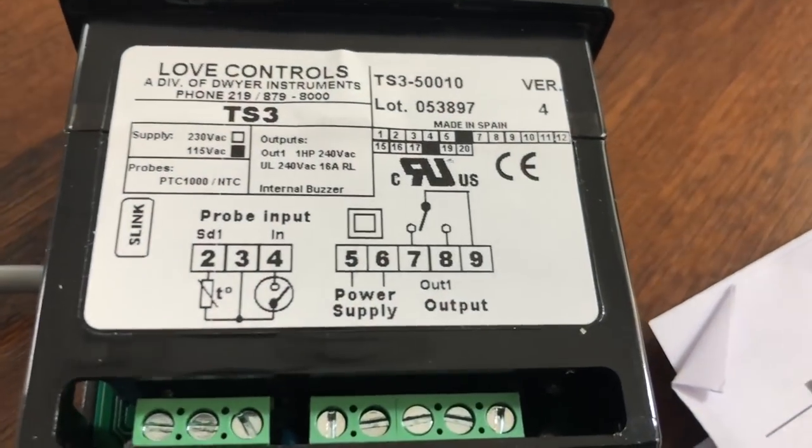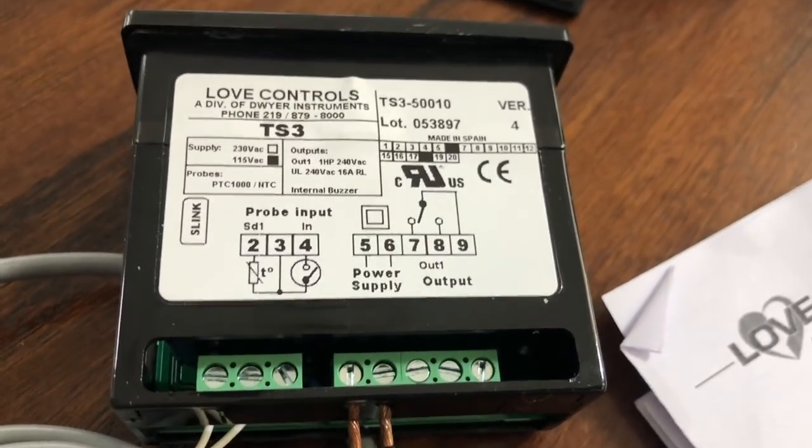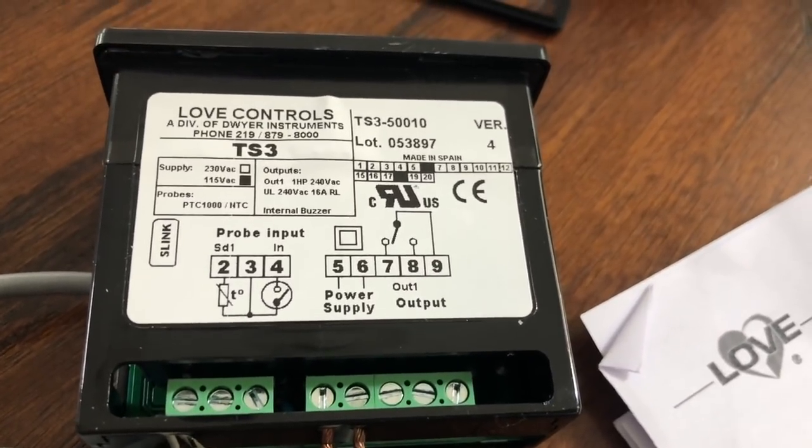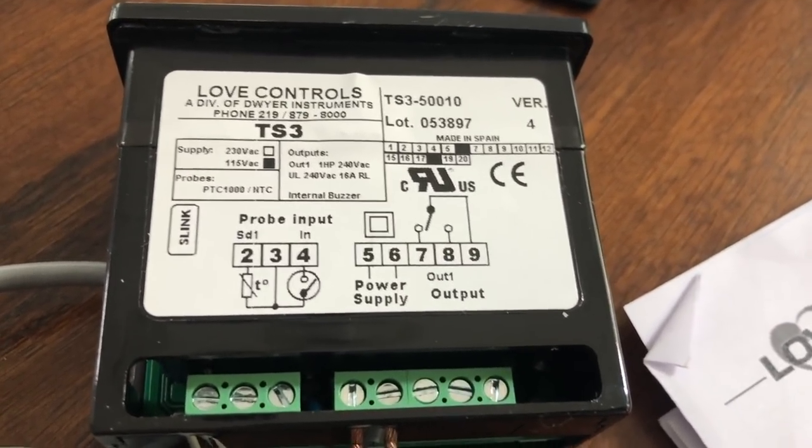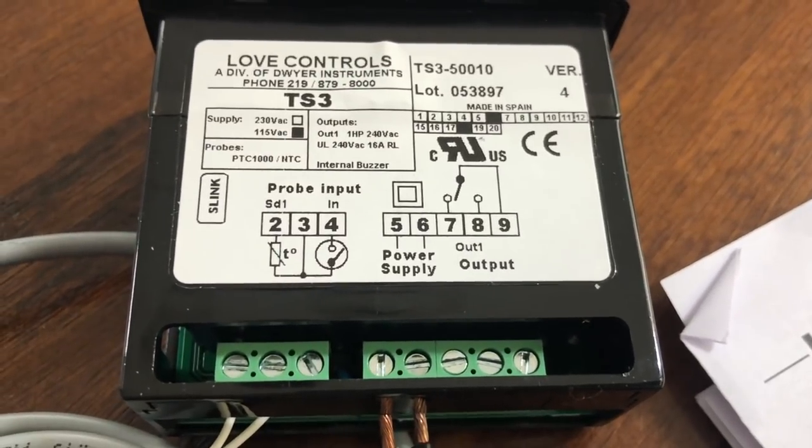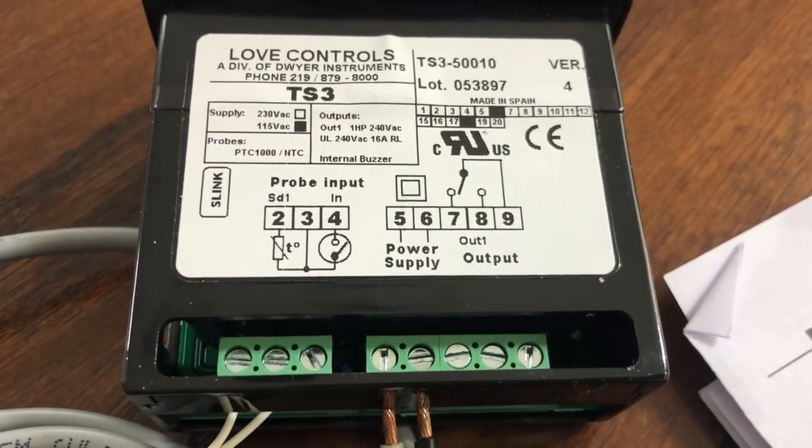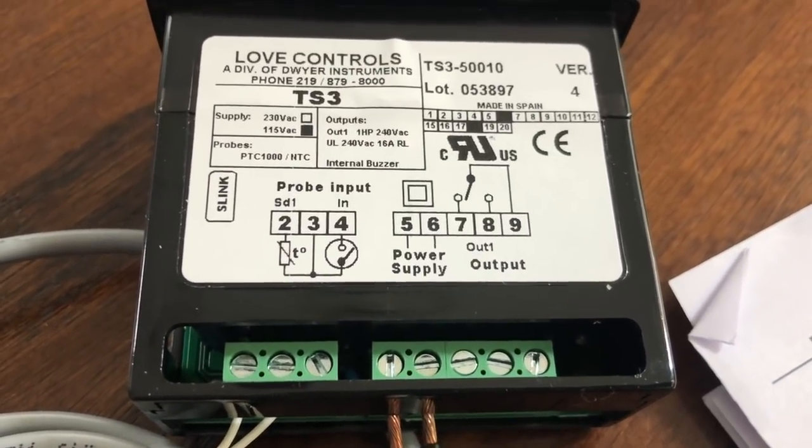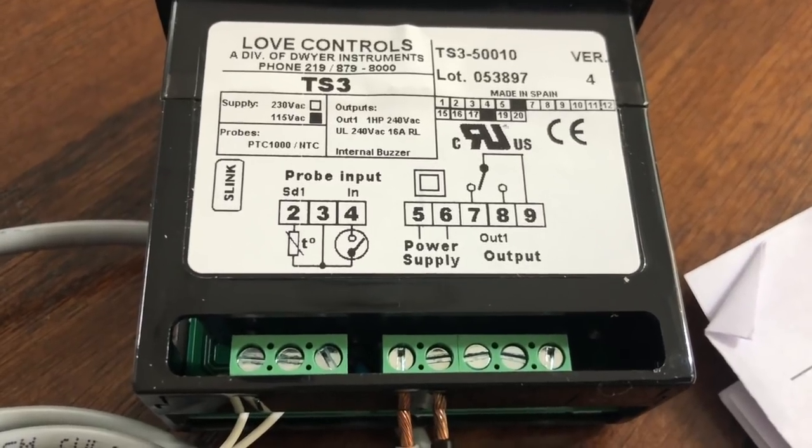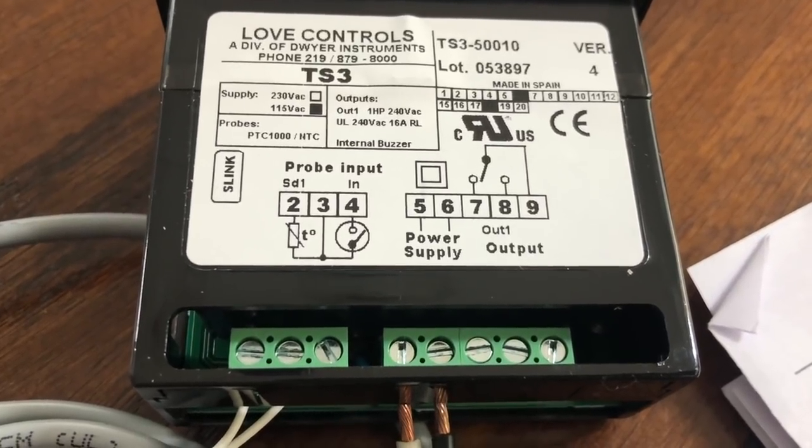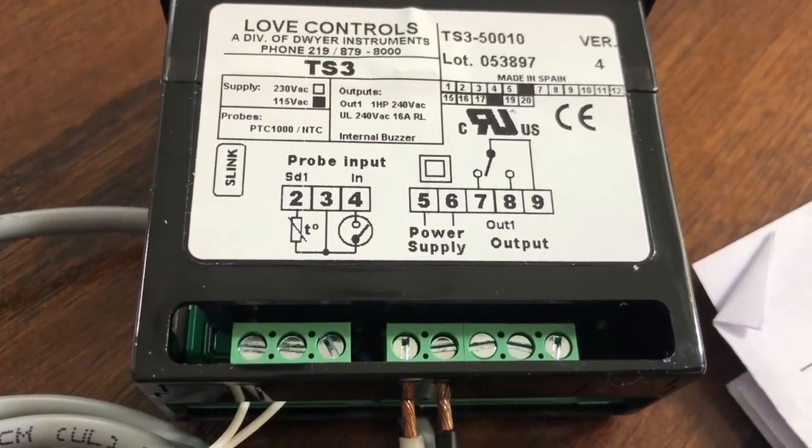Here we go, the inputs. You got your sensor on two and three. Now, this unit does not come with the sensor. You have to buy the sensor separately. Power supply between five and six, and then you got a dry set of contacts. You got nine being the common, and then you got normally closed on seven, and normally open on eight.